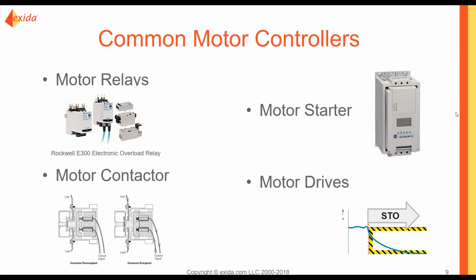Currently, for the motor starters in the field, there's a rather large variance between these products. They have many different capabilities, but what we've realized is there is not a lot of 61508 data available. But we do have some generic failure rate information in Exida, and I'll share with you closer to the end when we talk about what you do if nothing is certified and you can't find anything, because this really didn't start ramping up till 2016, 2017 at least.